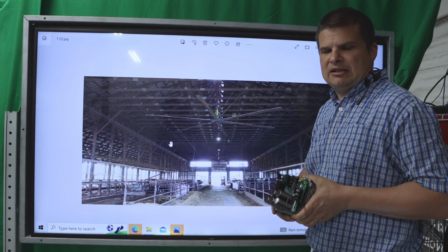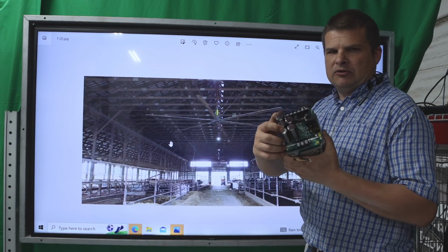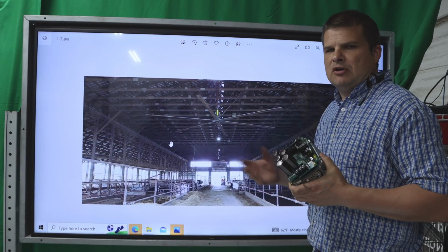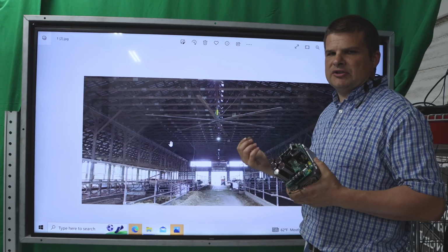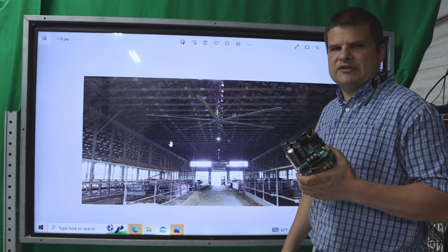We would recommend adding lightning protection to any kind of VFD, because what this bulged capacitor comes from is a temporary overvoltage. So that is the most likely thing to go wrong with a motor and VFD combination, is the variable speed drive, because this kind of stuff is just more sensitive to electronics.